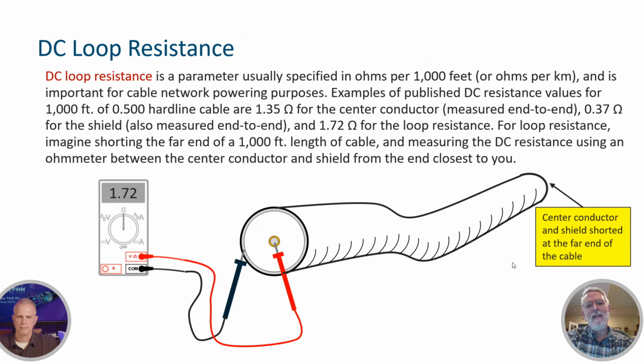And now you get down into that low resistance number, and your conventional ohm meter is going to be kind of iffy on its accuracy, especially because you've got to take into account the leads and the other stuff. And so it's the lab grade stuff that is used by the manufacturers to really characterize this. So for the loop resistance, just imagine taking that 1,000-foot piece of cable, you short circuit the center conductor and shield at the far end, and then you measure between the shield and center conductor with your ohm meter, and there's your loop resistance. That's it.